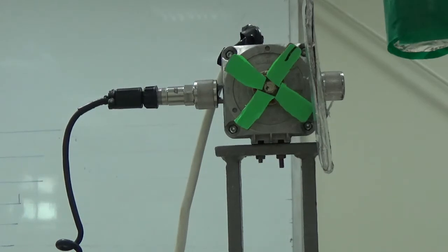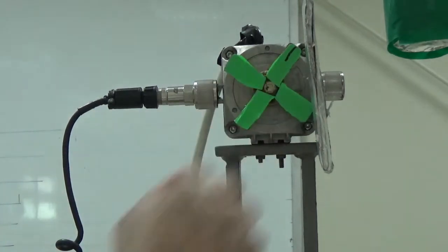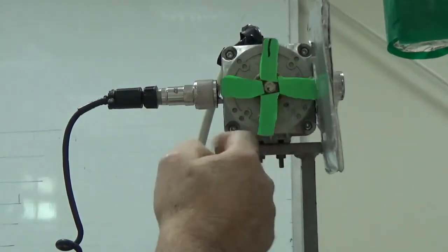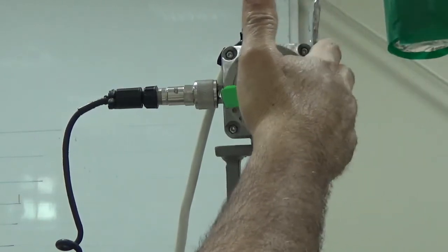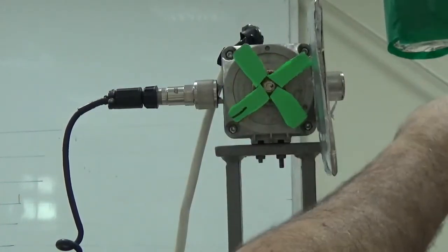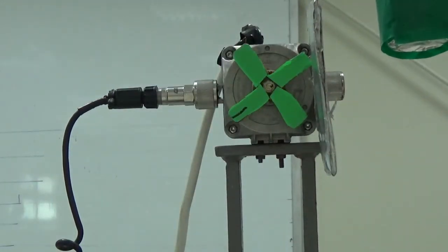Now here you can see there is a fan. It has got 4 blades, 1, 2, 3, 4, and this is a plate. The blades can touch this cover. If you press it, it will touch more. I will use this one to press it, then it will touch with more pressure. So let us start, and you will see the spectrum for this one, and we will note down the RPM also.